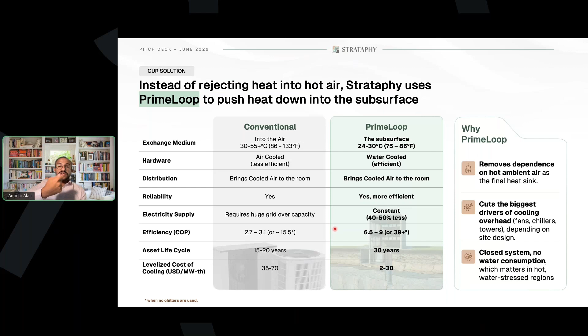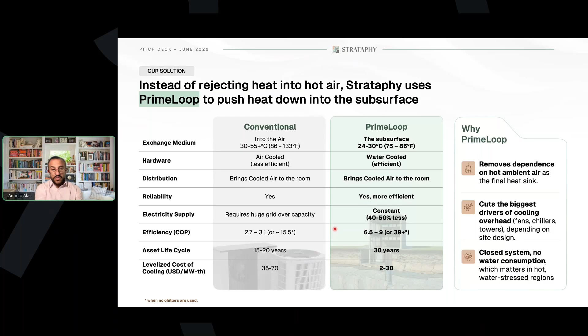For normal air chillers, the COP could be 2.7 to 3.1. Dry coolers, because they don't have compression, could shoot up to 15, 16, 17. Our system, if it needs compression and is connected to a water-cooled system, could be 6.5 to 8. Without it, it could shoot up significantly higher. The life cycle is also a big difference. Especially if you're under the sun and with dust, the life cycle could be significantly lower for air chillers versus our system. Ours live longer.